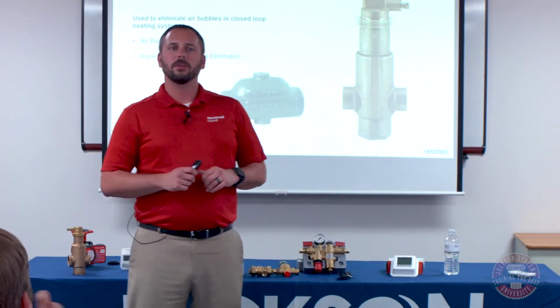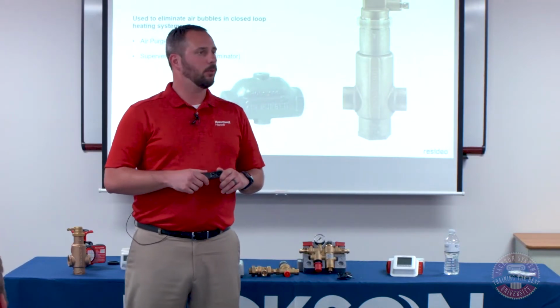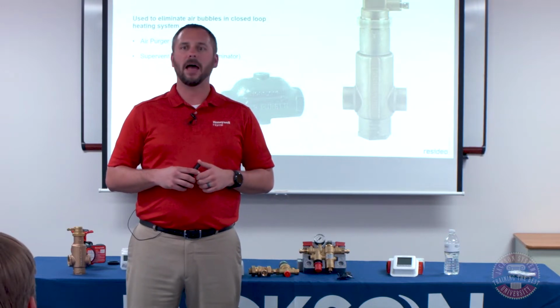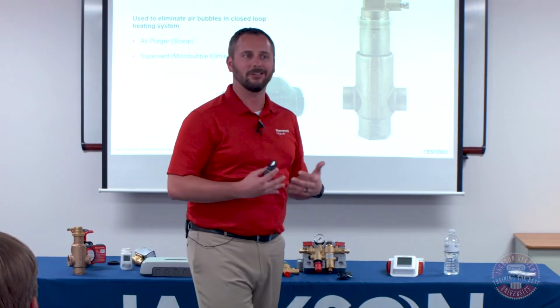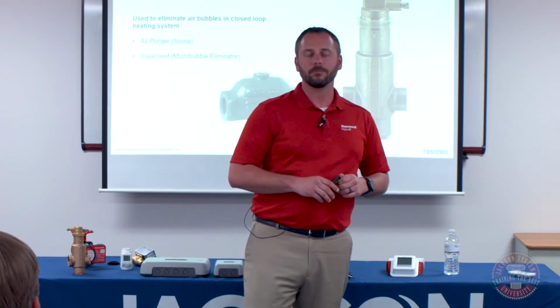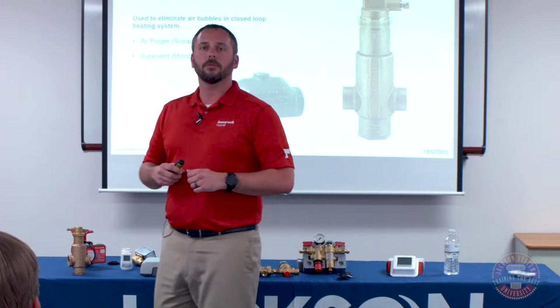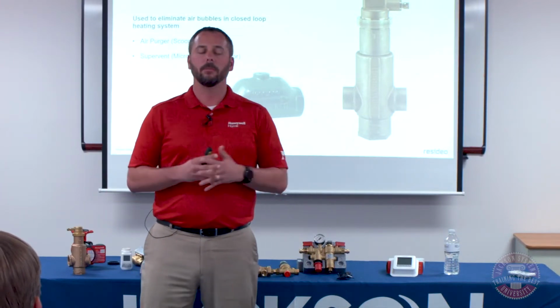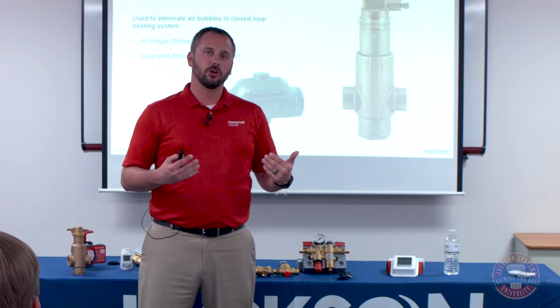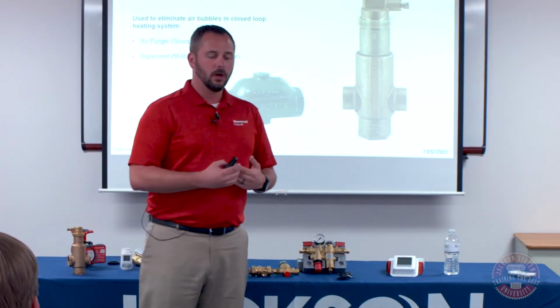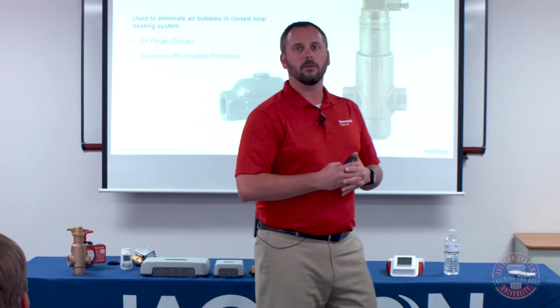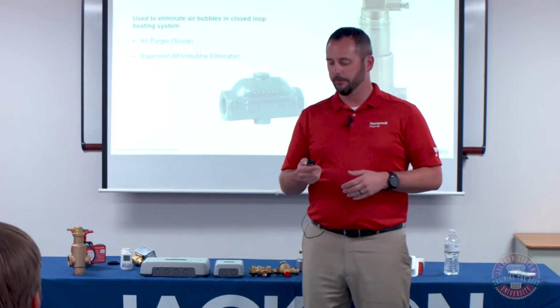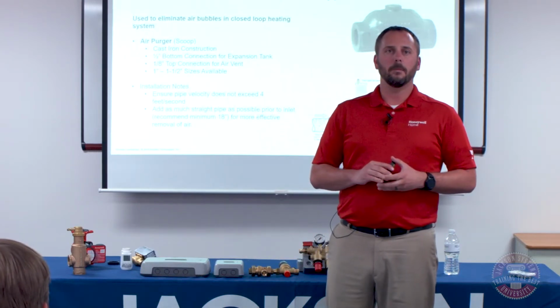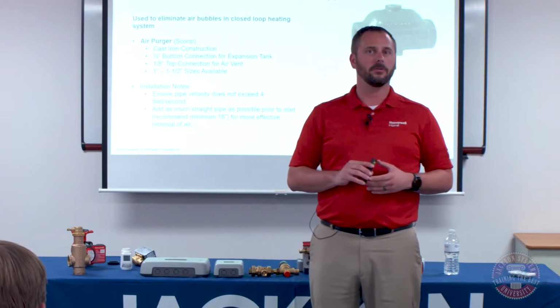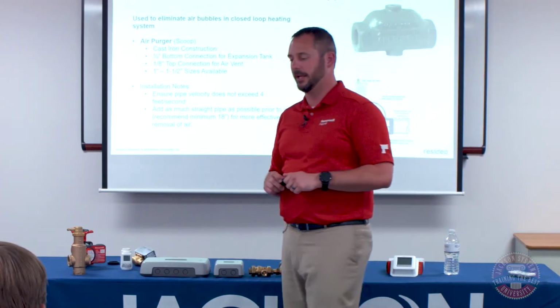The other piece: we've talked about two of the three things that we have in our boiler trim kit. We've talked about the fill valve, backflow, selecting pressure, and the expansion tank. The other critical piece is going to be air elimination. There are two different types of air separators, and we sell both of them. You're looking at an air purger, also commonly referred to as an air scoop. We also sell a Super Vent, which is a microbubble air eliminator. There are two major differences, both in price and functionality, between these two types of air elimination devices.